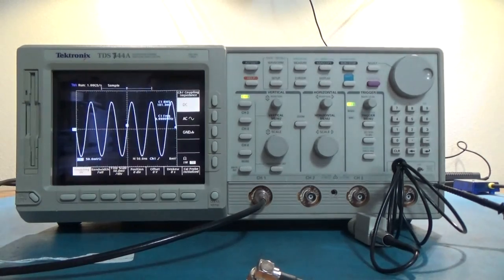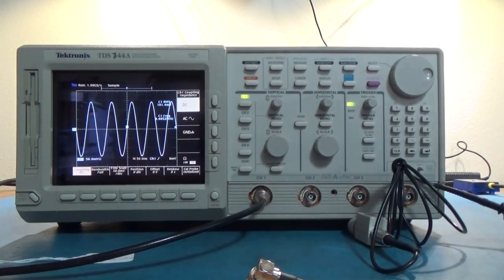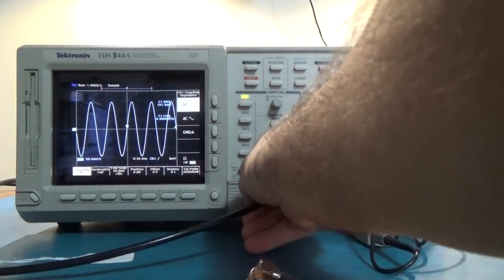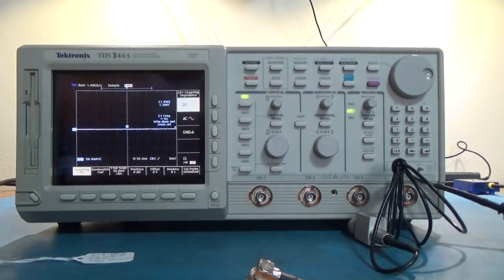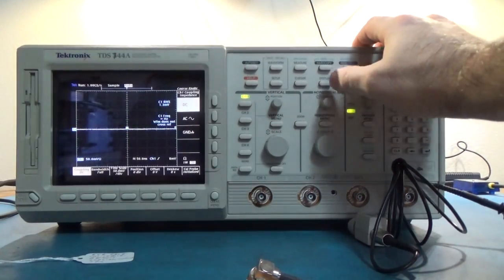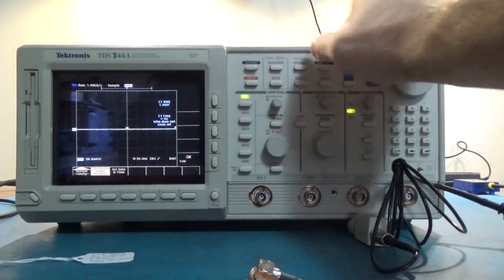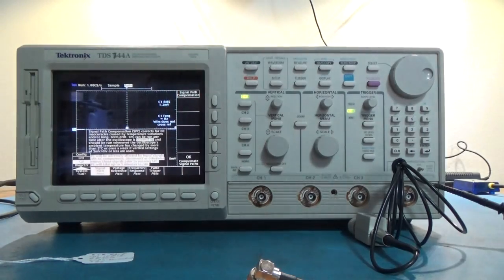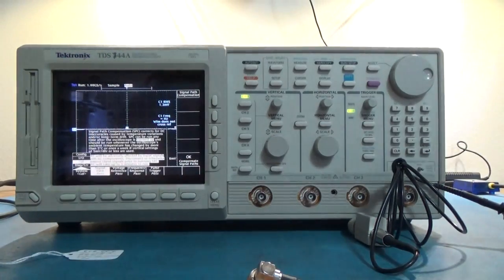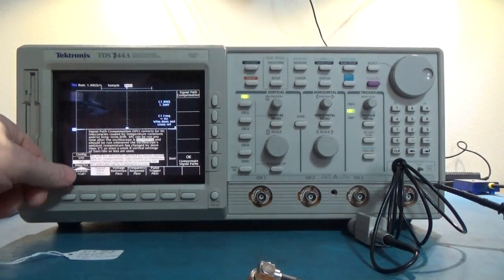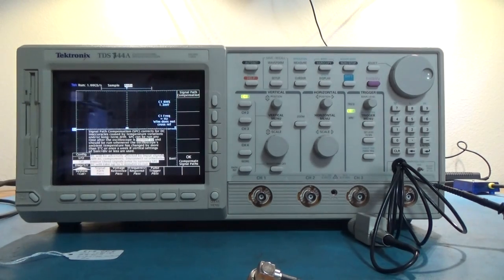But if you had a signal that was up like that, and you press the AC button. You'd expect it with center on the screen. That's telling you a relay is doing its duty. And then ground. That's what you kind of want to see. So you want to do that with all the channels of a new scope that you get in. You also want to run the SPC. Which I won't do now. Because that will take a long time.